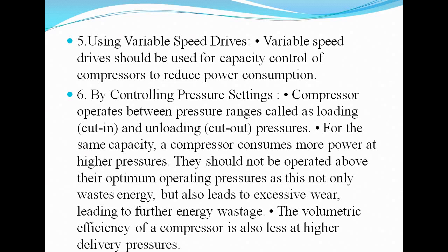So if the pressure increases, there would be an increase in energy consumption of the compressor. They should not be operated above their optimum operating pressures, as this is not only a waste of energy but also leads to excessive wear, leading to further energy waste.